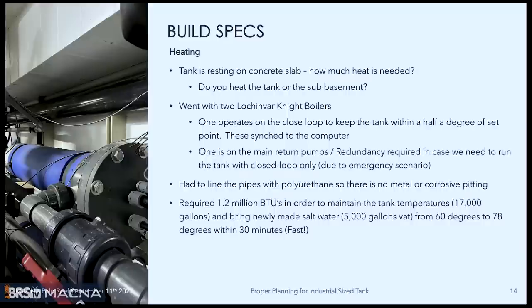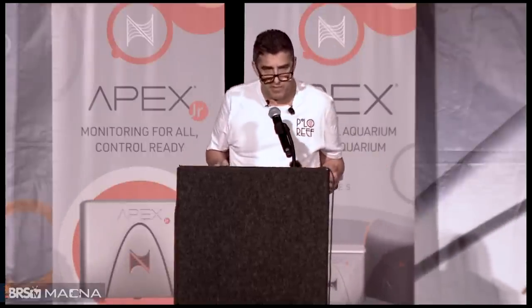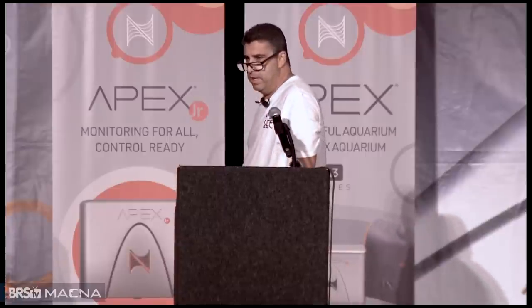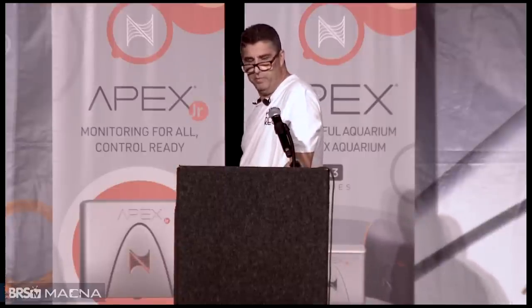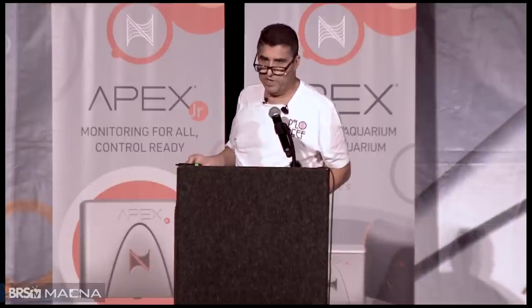I have something here to remind me that not only do we have to service this computer all the time, but we have to maintain spare parts and spare inventory because things happen. And just the other day, we had a lightning strike in the house. It started in late August, and the ground had about 10 to 20 volts in it, and people were getting shocked and all sorts of things. And believe it or not, the lightning took out the brain of the computer, and we had to replace the brain, and we just happened to have an extra brain. That will be a chub item, but along with the other damage. But the point is spare parts, and I don't mean just on the computer. I mean on everything. We have a spare on every pump, on every part. Can't take a chance at this scale.